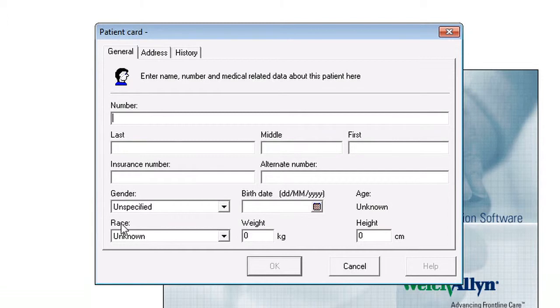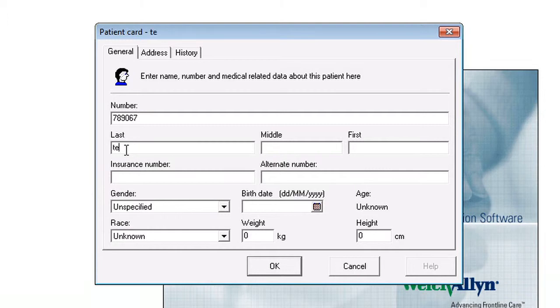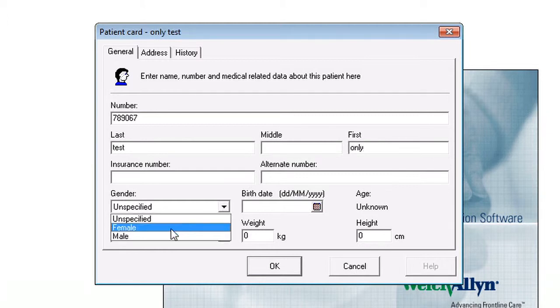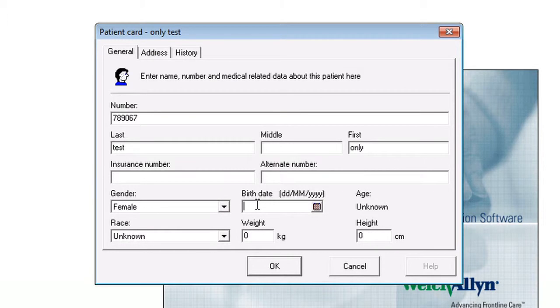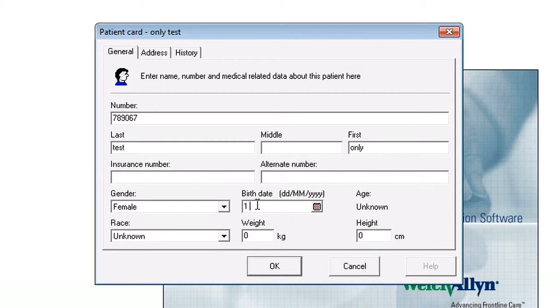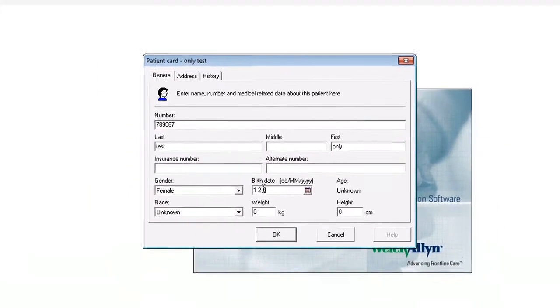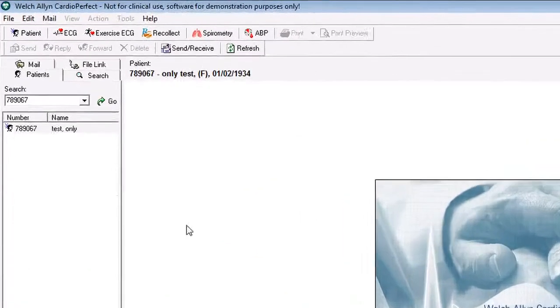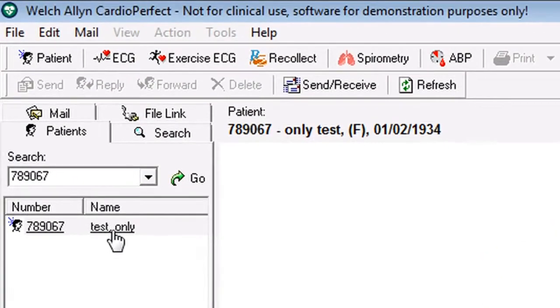fill in the patient ID number, NHS or other, the last name, the first name, the gender, and the birth date. And then click OK. Their details go into the memory and they'll be there next time the patient comes in for another test.